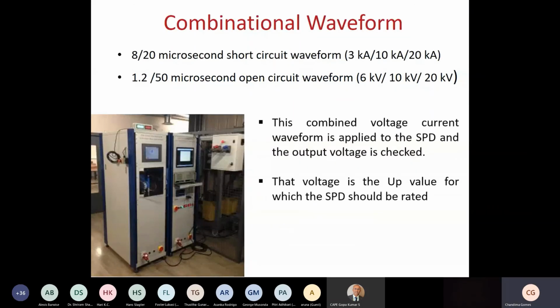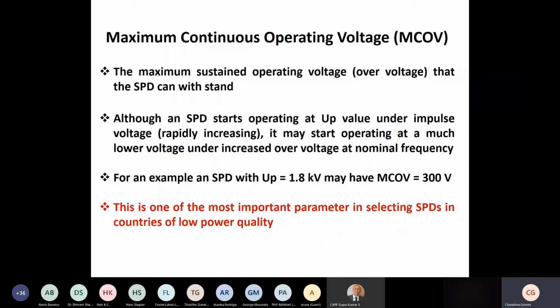This is a combinational waveform generator. I'm going a little faster. And then the maximum continuous operating voltage, which is a very important parameter. Actually, it tells you, in the case of a sustained overvoltage at nominal frequency, what is the maximum value that the SPD can withstand. Now, for example, for SPDs with UP equal to 1.8 kV, the MCOV may be like 300 volts or less.